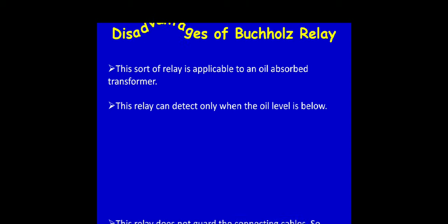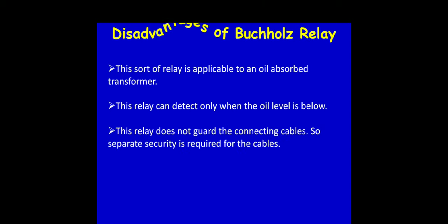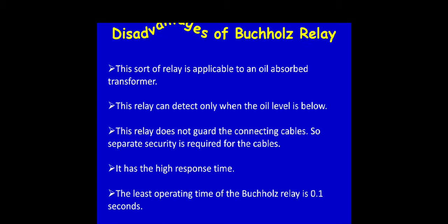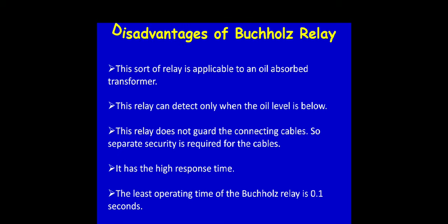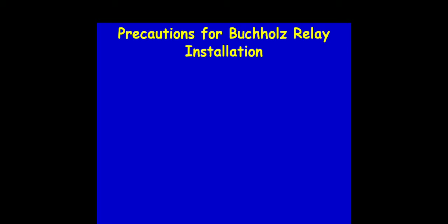Disadvantages of the Buchholz relay: first, this relay is applicable only to oil-immersed transformers. Second, this relay can only detect faults when the oil level drops below a certain level. Third, this relay does not guard the connecting cables, so separate protection is required for cables. Fourth, it has a high response time — the minimum operating time of the Buchholz relay is 0.1 seconds.